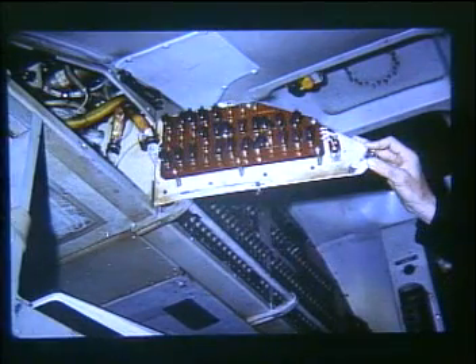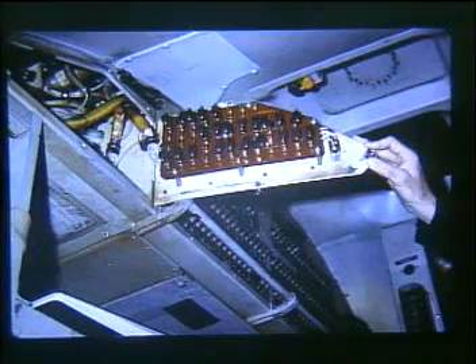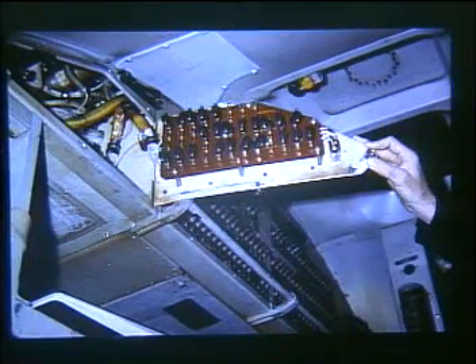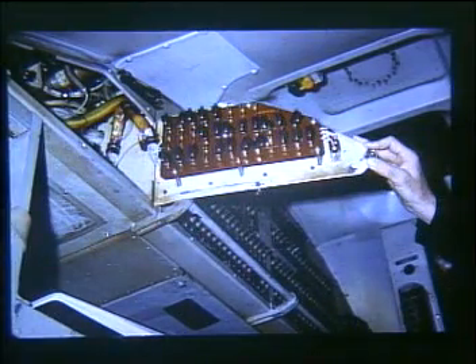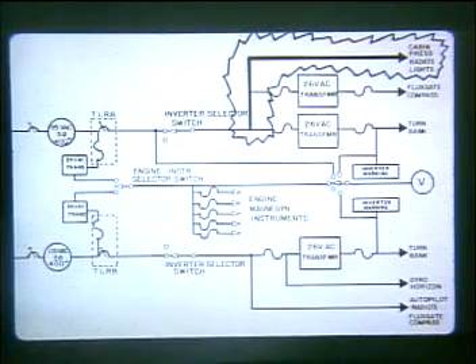The AC fuse panel contains fuses for the captain's, first officer, and engine instruments, and for AC radio feeds, pressurization, and some miscellaneous AC requirements. Prior to the 26-volt AC step-down transformer, 115-volt AC is taken off to supply power to the automatic section of the cabin pressure control system, certain radio equipment in the radio rack area, and for fluorescent lights in the blue room. Fuses to protect the cabin pressurization and lighting system are located in the AC fuse panel. The majority of the AC fuses to protect the various AC sections of the radio equipment are located on the aft post of the radio equipment rack.